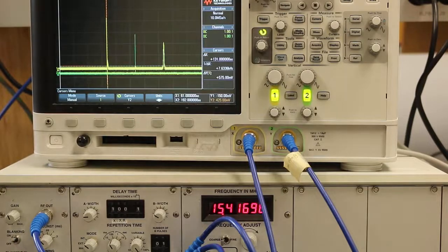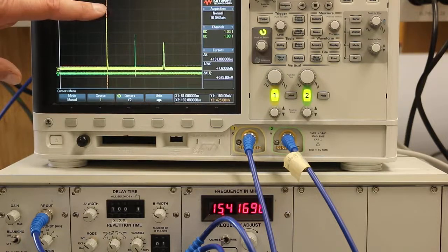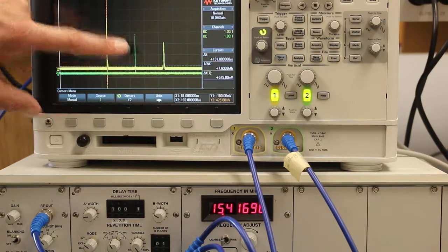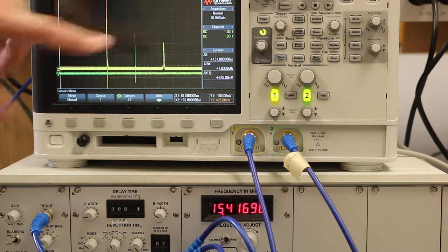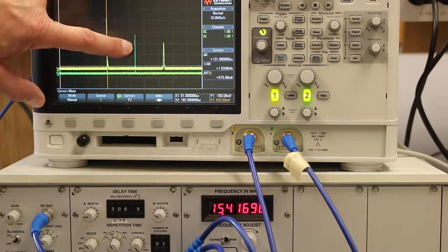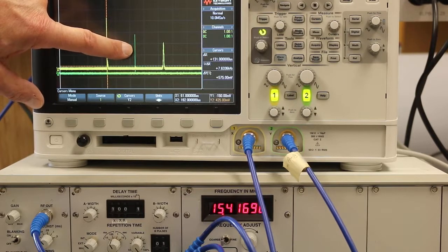And this is always a very interesting part of pulse NMR because remember, this is where the A pulse is actually on, this is where the B pulse is actually on. And what I mean by on, when these pulses are on, it means RF is actually getting applied to the sample at 15.41 megahertz. But when the pulses are off, there is no RF. So interestingly, this B pulse is when the last RF ever got applied to the sample in this configuration.